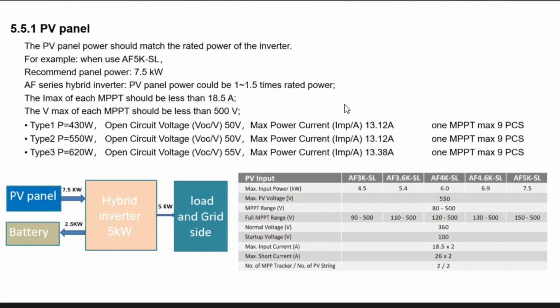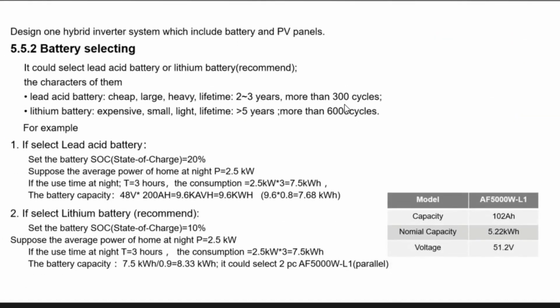And also, for example, for the 5K single phase one, you apply about 1.5 times the PV size. Normally the hybrid inverter rated power is 5K to the load, and the excess energy will be charged to the battery at the same time. So after you consider the calculation of the PV side, the next step is to design the battery side.